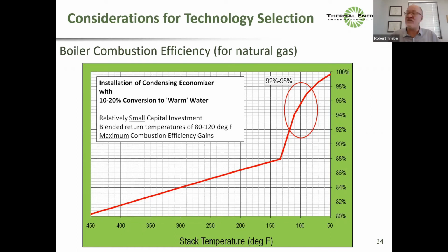So then you'd have to have some controls and make sure that anything cold is going through the stainless steel condensing economizer, because in a case like that, you can also preheat in the condensing. If everything's cold, you could put it all through the condensing economizer and then all through the hydronic boiler. So it can be done, Mark, but that comes down to a controls question.